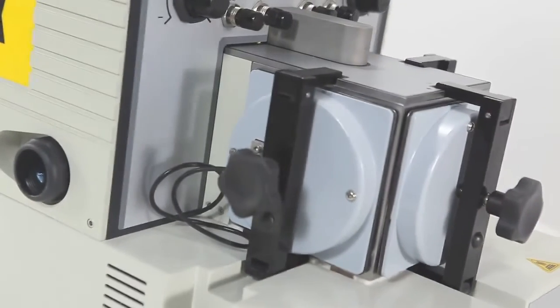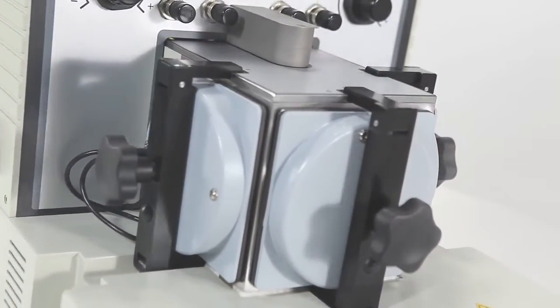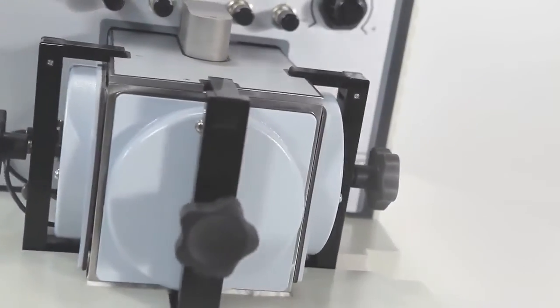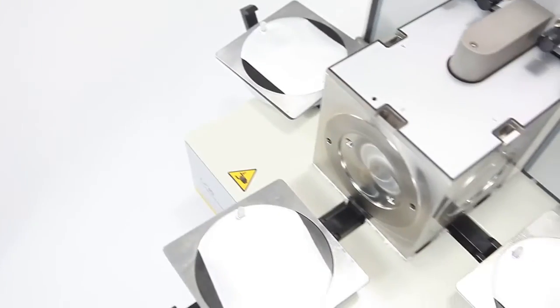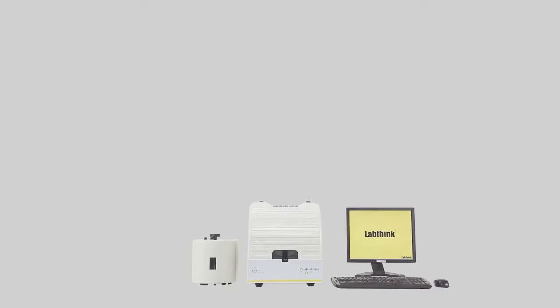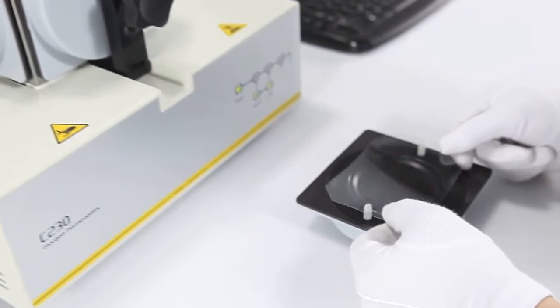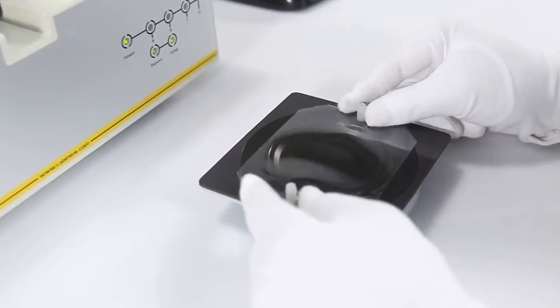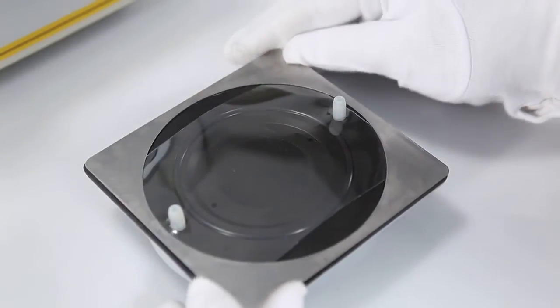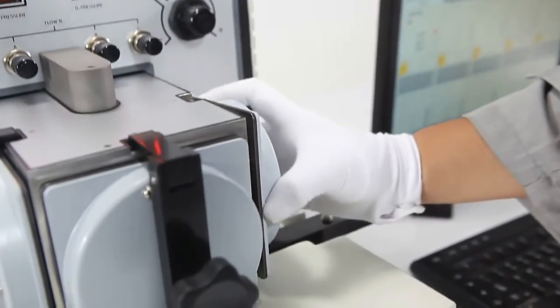C230 has three independent test cells which can test three same or different specimens simultaneously. According to standards, the instrument can be connected with multiple satellite instruments so that more specimens can be tested simultaneously. Reference films are available for system calibration, which guarantees the accuracy and universality of test data.